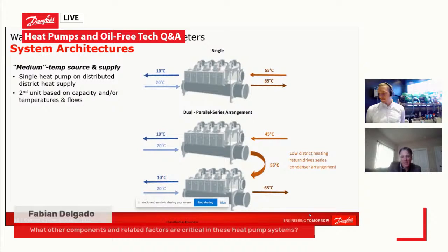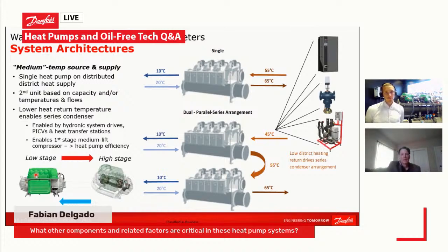And this is also tied to the question earlier on why we are focused on district energy systems today. The optimal solution for an oil-free heat pump system, and this can be true for individual buildings as well, but it's more common in district energy systems, is based on having a lower heating return water temperature. A lower heating return water temperature enables us to utilize different optimized compressor technologies for the low stage and then the high stage. That in turn means a more efficient heat pump system.